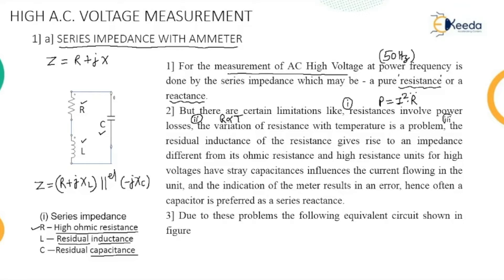There is another problem: residual inductance and stray capacitance. These two parameters influence the current passing through the unit. This residual inductance gives rise to an impedance different from its ohmic resistance, and high resistance units for high voltages have stray capacitances. The effect is that the indication of the meter results in an error — we will not get a proper reading.